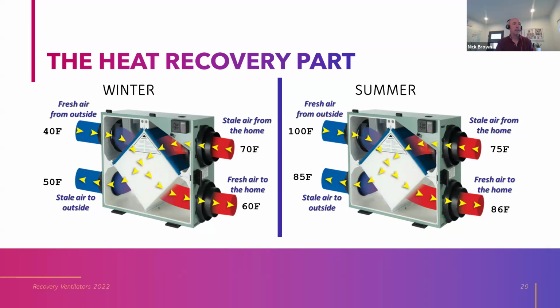I kind of find that putting some numbers in an example really illustrates it better. Keep in mind what's happening here too. The fans generate heat. They move air, but they also generate heat. And some of that heat is going into your space. For that reason, in winter, recovery ventilators generally perform more efficiently than in summer because you're getting that fan heat energy helping heat your outside air, whereas it's taking you in the wrong direction in summer. Just something to think about.